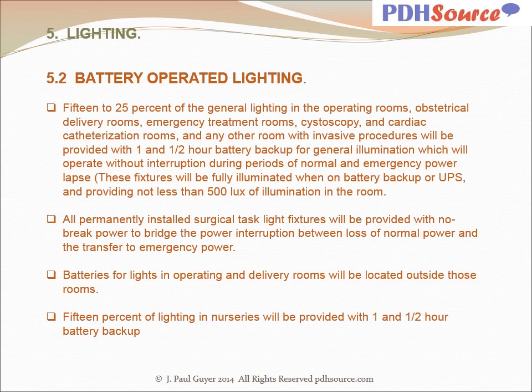These fixtures will be fully illuminated when on battery backup or UPS and providing not less than 500 lux of illumination in the room. All permanently installed surgical task light fixtures will be provided with no-break power to bridge the power interruption between loss of normal power and the transfer to emergency power. Batteries for lights in operating and delivery rooms will be located outside these rooms.